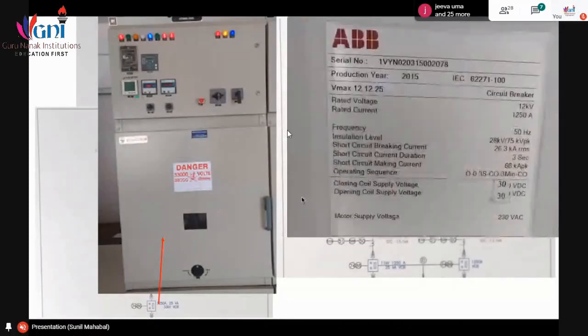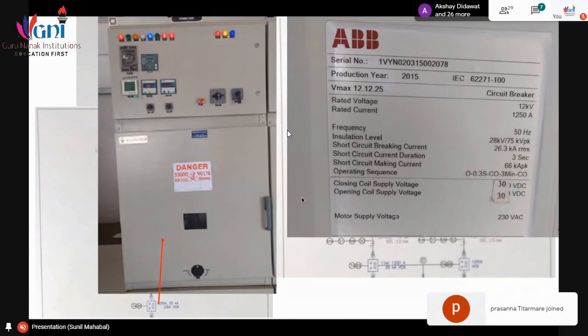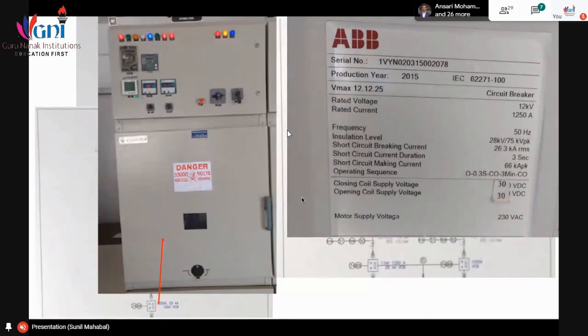And if you see the nameplate in detail, here it is operating at 1250 ampere, 12 kilovolt. And if you notice here, the short circuit breaking current is 26.3 kiloampere, whereas short circuit making current is 66 kiloampere. So why is there a difference? It is almost 3 times. The reason is that when the healthy circuit is working, the normal healthy current is flowing through the circuit and circuit breaker. And then when a fault occurs, the current will gradually increase and reach that maximum level. But during that path, we can break it.